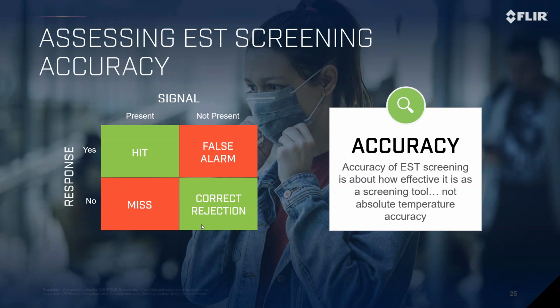A correct rejection would be the camera says, hey, you're within tolerance, you're not running anything high, you're not out of the norm, you're not that anomaly, you're fine, and then tested against a medical grade thermometer, same thing, this person does not have an elevated body temperature. That would be a correct rejection. So those are what you're going to have the most of. You're going to have people that come through that are fine, their temperature is fine, and they pass through, right? So correct rejection, you're good to go, you're good to pass.